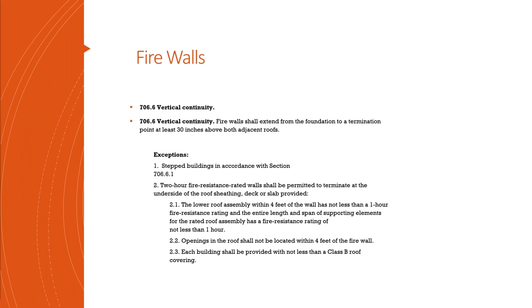And then each building shall be provided with not less than a Class B roof covering. So when you have a 2-hour firewall, in order to terminate it this way, like butterflying out, all these provisions have to be in place. That one's not a pick and choose. So yes, that's commonly called butterflying it or butterflying out. And again, just some visuals to help you through with what that might look like.